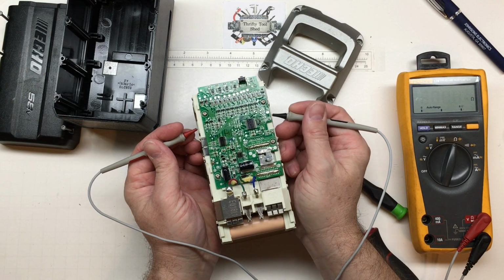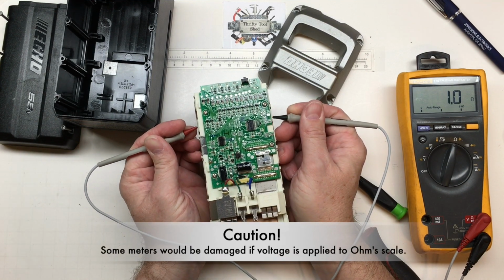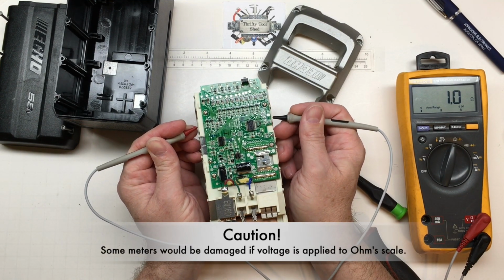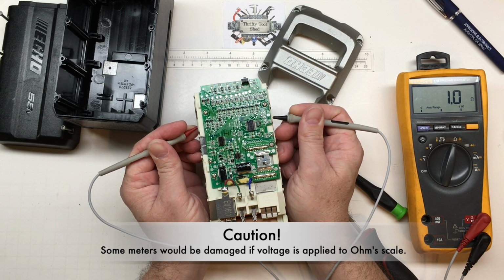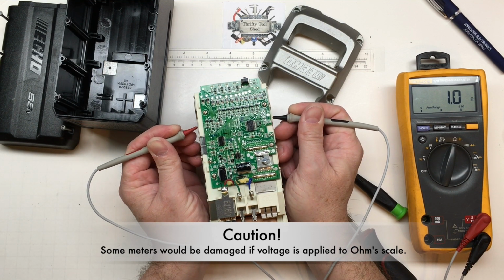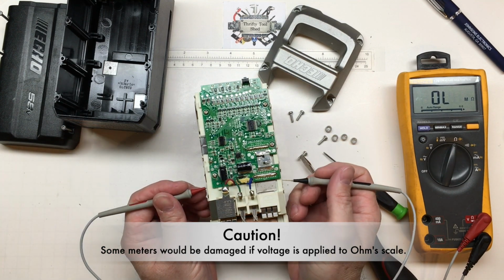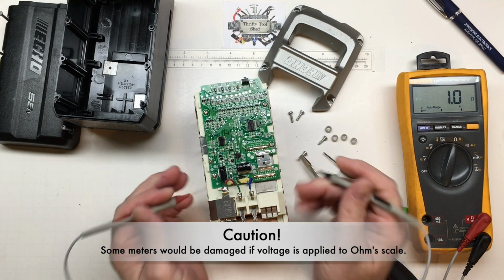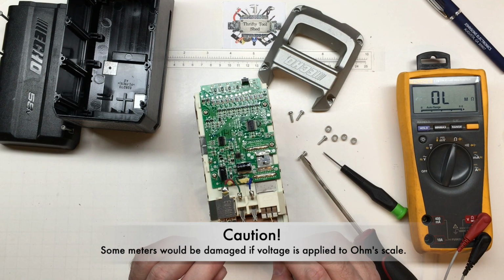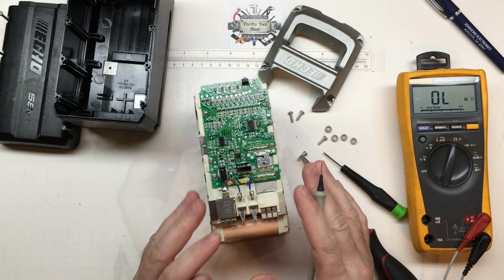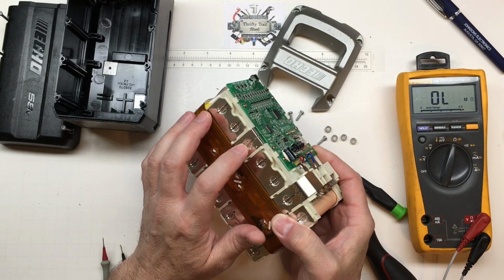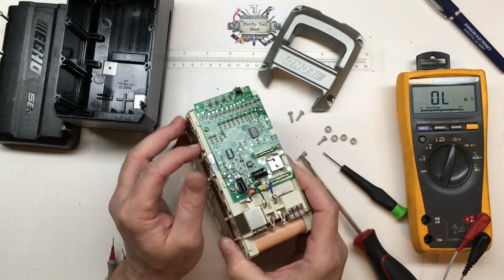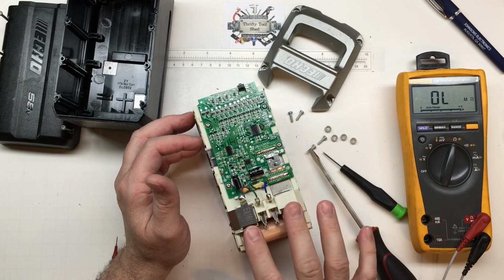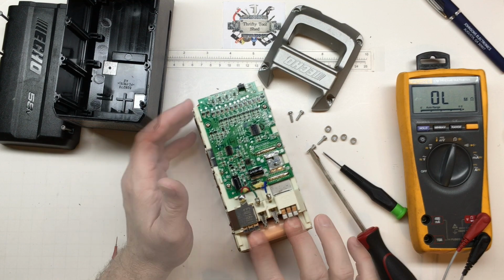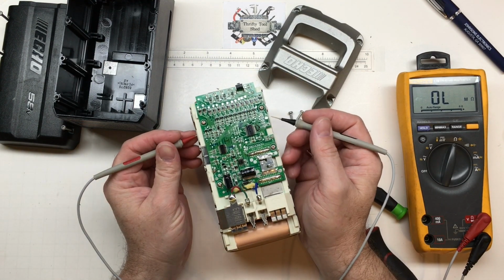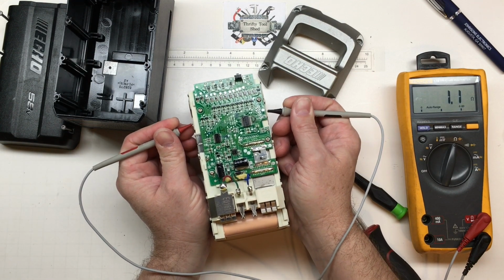One thing I want to do is ohm it out. You've got to be careful ohming with voltage still on there, but this is a high-end meter, and we see that these cells not only read 0 volts, they're showing like 1 ohm, just like a dead short. That's the only reason our 50 volts is actually getting out. If these cells had completely opened up, like a CID activation or something internally in the cell, we would have been open and not getting hardly any voltage to the battery output terminals.